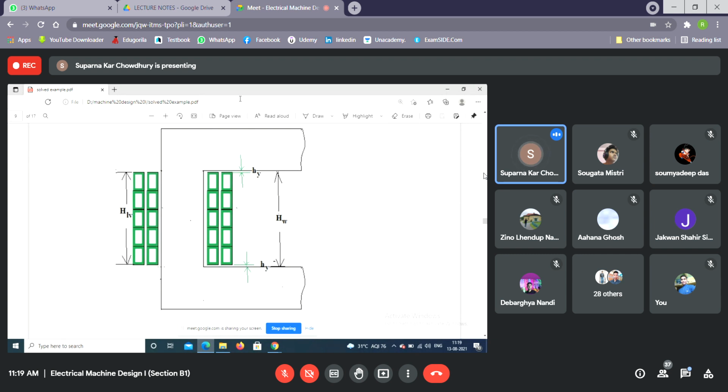But if you see the reel of thread available from the shops, then you will see that it is wound around the cylindrical paper spool, but it has a twist in a twisted fashion, so the grip is much more. So in helical winding, there will be an intentional twist equivalent to the height of one turn, and this twist makes the mechanical grip of the helical winding better. So that is the main difference.